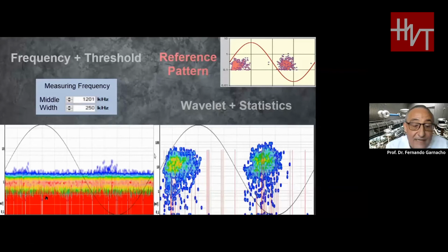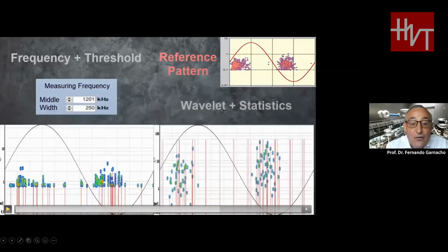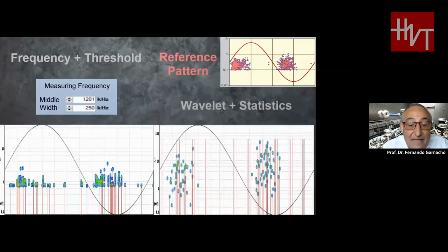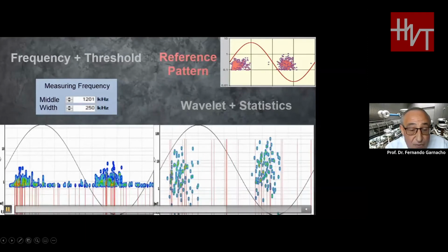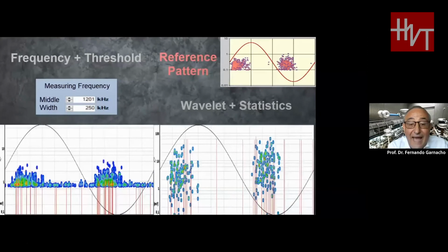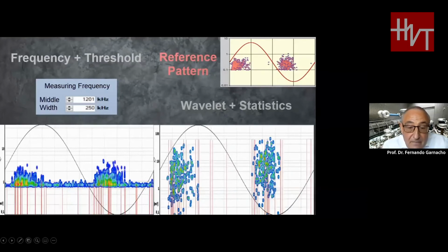We can see the video. Now we have the opportunity to see again the PD pattern, because we have moved the measuring central frequency to 1.2 megahertz. Of course, using the wavelet technology, it doesn't matter, it's not affected.